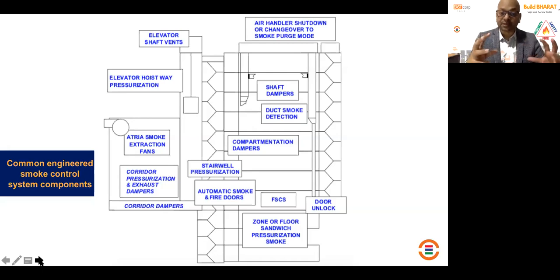Because we are creating a differential pressure, and that differential pressure can only be achieved when you do that engineering calculation rightly. Your fire doors are the interface between your lobby and the staircase. If you keep the door open, will the pressurization work? No, it will not have that efficiency, because you will have a lot of smoke or air to compensate in that pressurization. So the pressure difference we are looking at, 50 Pascal, will not be achieved if a door is kept open.